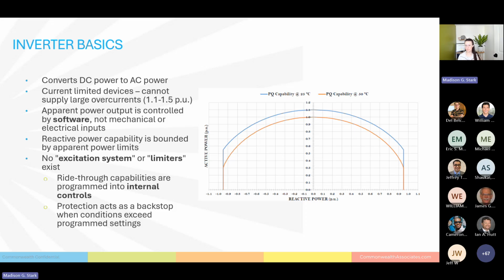If you're not familiar with the per unit system, what that means is it's like 110% to 150% of their rated capacity. So a synchronous generator can output 3 to 6 times their nameplate rated capacity for current, but inverters cannot do that. So that's a huge limiting factor on an inverter that has to be planned for. The apparent power output for an inverter is not controlled by excitation and rotating machine type inputs. It's controlled by software programmed inside the inverter itself. So this reactive power capability for the generator is bounded by these apparent power limits, which are controlled by the internal controls, the internal software of the inverter.